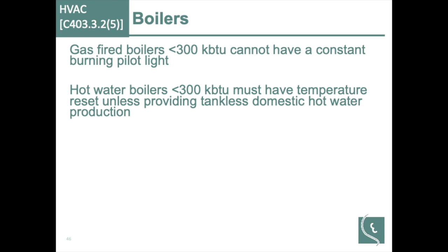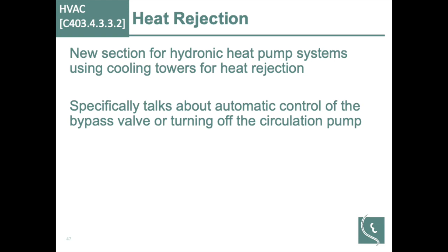Heat rejection. Not sure how many systems this would necessarily apply to, but noting that when you're using cooling towers to reject heat for heat pumps, there are some additional controls for the bypass valves and circulating pumps. Again, with heat pump applications, try to optimize that and reduce the energy consumption of the system when it's not needed.